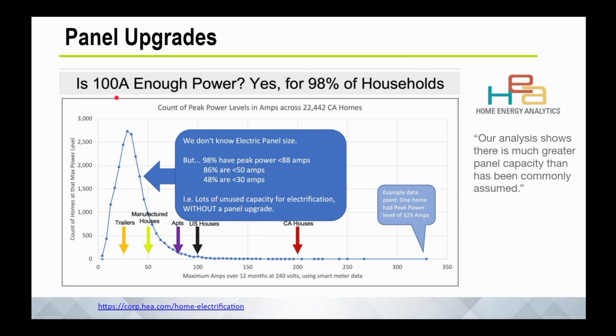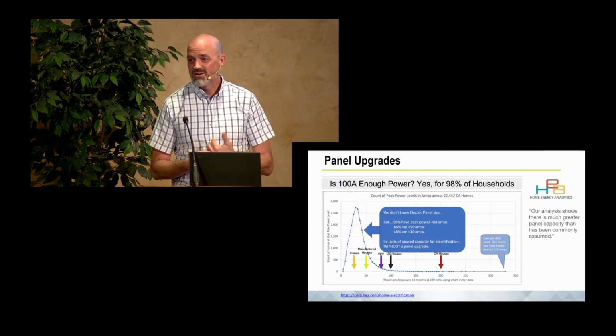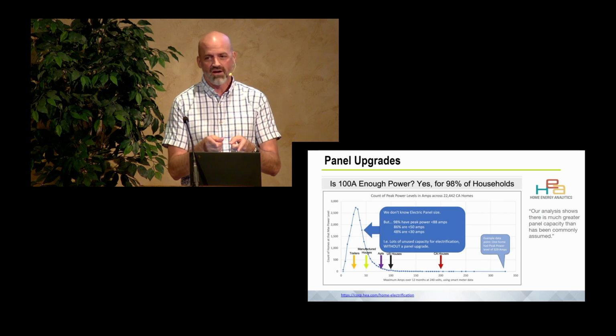Is 100 amps enough power? Yes. This blue curve is sample data of what those homes are using—here's the peak. 98% of them are under 90 amps, 86% are under 50 amps, and just under half are under 30 amps. Most of those homes have 200 amp panels—plenty of capacity. I'm not saying the California grid doesn't have problems, but the breaker panels are not the problem.